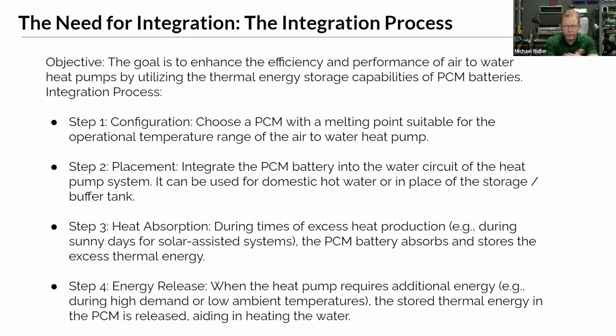For example, off to my left here, we have an air-to-water heat pump, so that PCM battery is designed to phase change at 58 degrees C because that's the capability of that phase change battery. If I'm going to put it on a boiler, I could use a different unit—like a P60 or something higher than that. If I was going to do it in a water-to-water application, I'd probably want a 43, because those units are really ideally suited for 110 degrees.